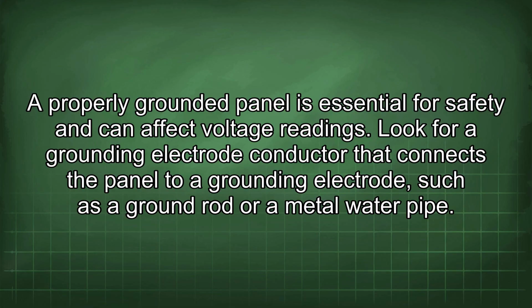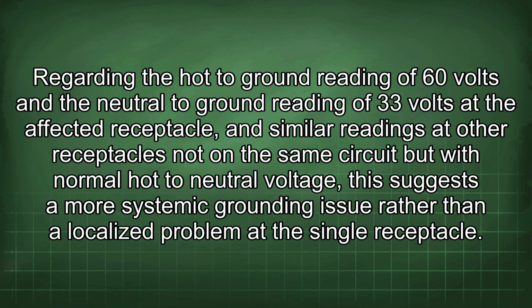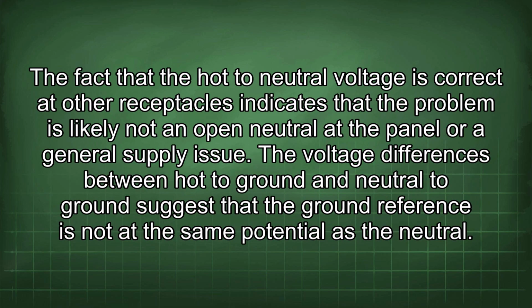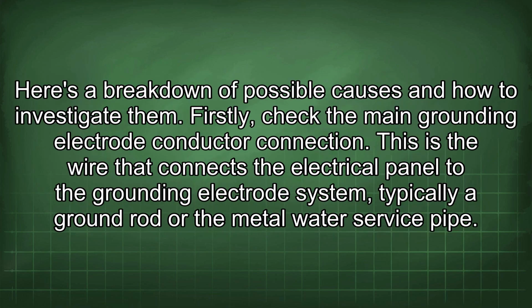Regarding the hot to ground reading of 60 volts and the neutral to ground reading of 33 volts at the affected receptacle, and similar readings at other receptacles not on the same circuit but with normal hot to neutral voltage, this suggests a more systemic grounding issue rather than a localized problem at the single receptacle. The fact that the hot to neutral voltage is correct at other receptacles indicates that the problem is likely not an open neutral at the panel or a general supply issue. The voltage differences between hot to ground and neutral to ground suggest that the ground reference is not at the same potential as the neutral. Here's a breakdown of possible causes and how to investigate them.